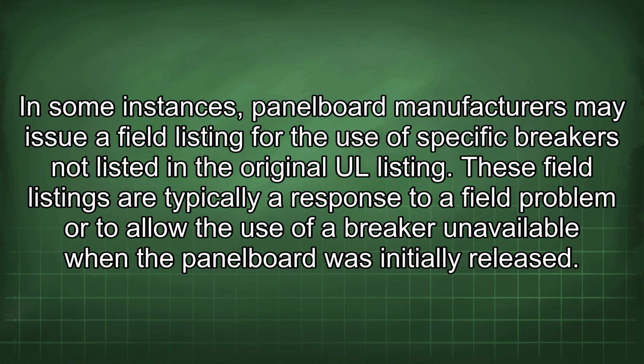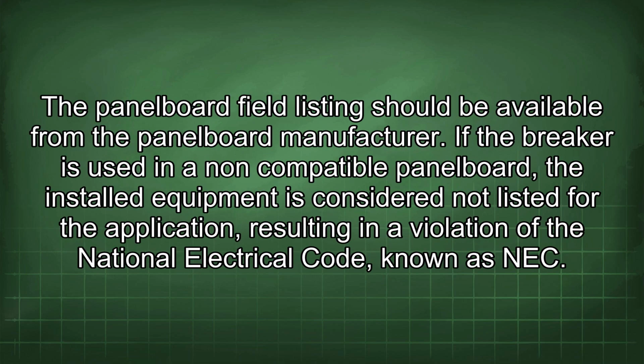In some instances, panel board manufacturers may issue a field listing for the use of specific breakers not listed in the original UL listing. These field listings are typically a response to a field problem or to allow the use of a breaker unavailable when the panel board was initially released. The panel board field listing should be available from the panel board manufacturer. If the breaker is used in a non-compatible panel board, the installed equipment is considered not listed for the application, resulting in a violation of the National Electrical Code, known as NEC.